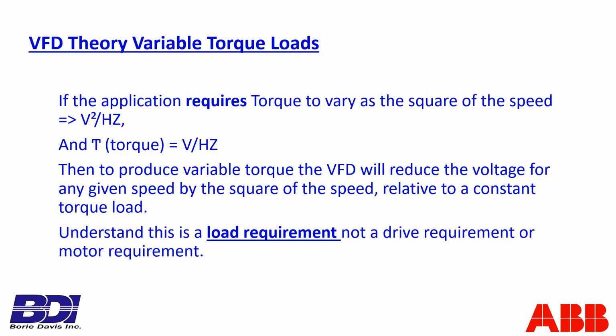Okay, so if I see that happen, that this thing is tripping out on overcurrent at very low hertz, like 1 or 2 hertz, that tells me that this thing doesn't have enough torque to break away, and I will change the volts per hertz to linear to give me more breakaway torque, and I'll share that more as we get into the drive section. Thank you.